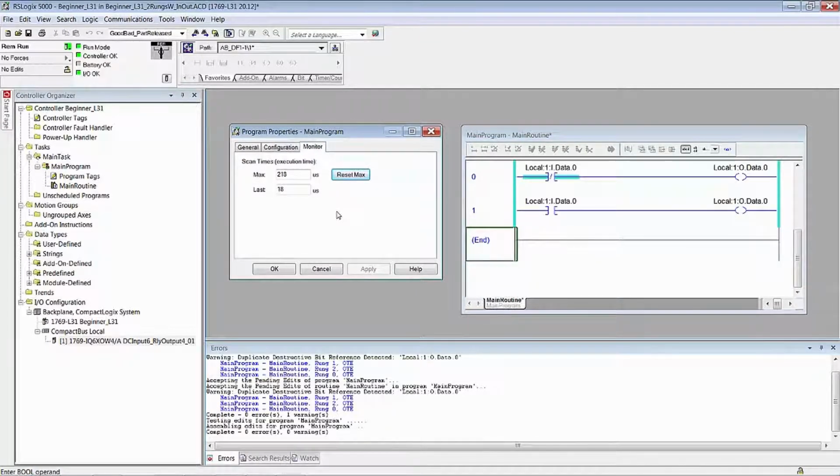And you see that the scan is not exactly 20 milliseconds. If you're splitting hairs here, what we used to call nitpicking, you could never get the scan time to line up with the RPI, so there was not this problem, simply because the scan rate is not consistently at one fixed rate. There's other things going on in the background. You can see that no matter what you do here, the I/O update is going to fall in between rung 0 and rung 1 once in a while. Even with 750 milliseconds for an RPI, it's still going to happen once in a while. And that could mess up your program.